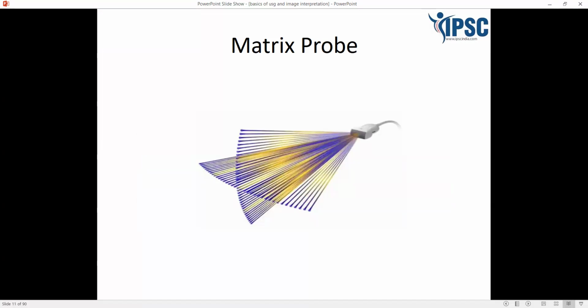Then there is something known as a matrix probe. So what are matrix probes? Matrix probes are probes in which the piezoelectric crystals are arranged in multiple directions, that is, in a horizontal fashion and in a vertical fashion. Now, how does this help? Since there are more ultrasound beams produced in different directions, more beams are reflected back to the probe. Hence, the resolution increases to a much greater extent. So, matrix probes have more piezoelectric crystals to produce more ultrasound beams and hence more resolution.